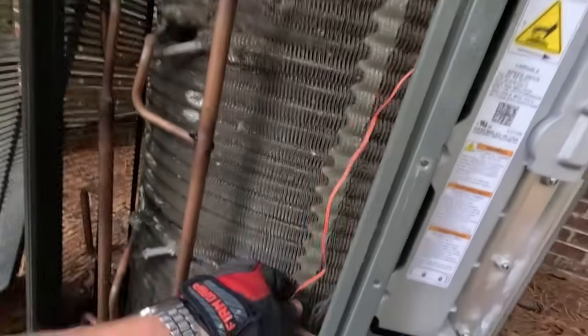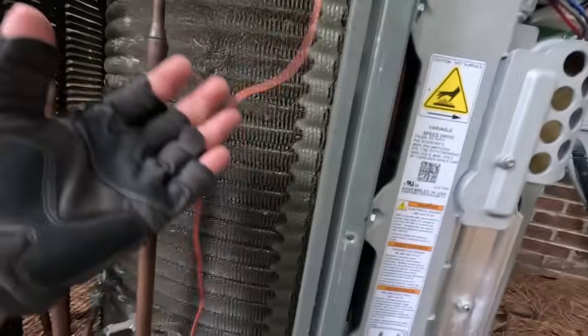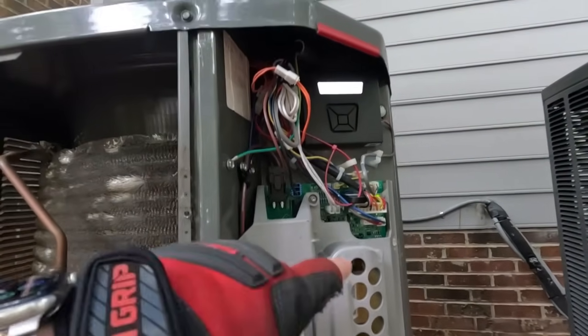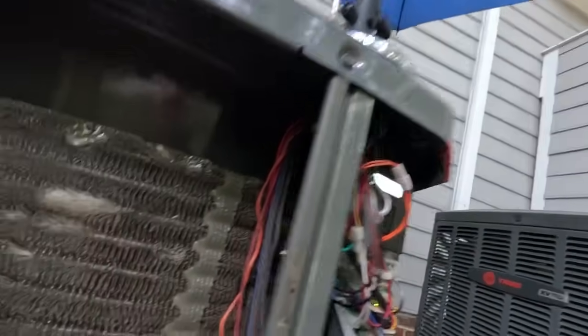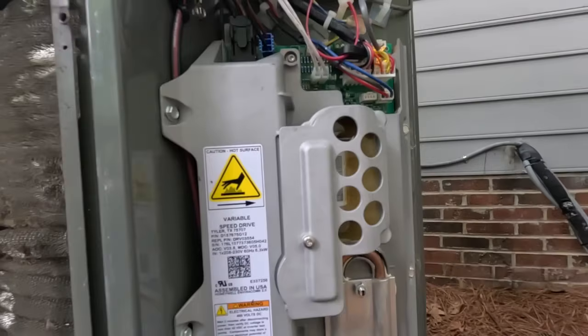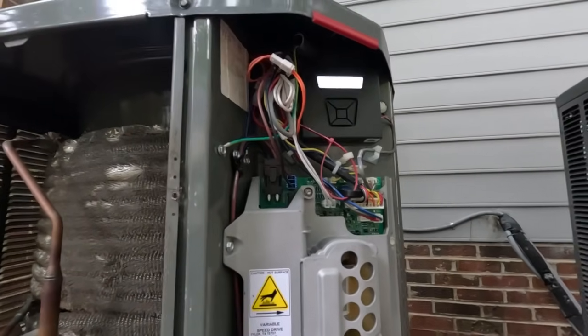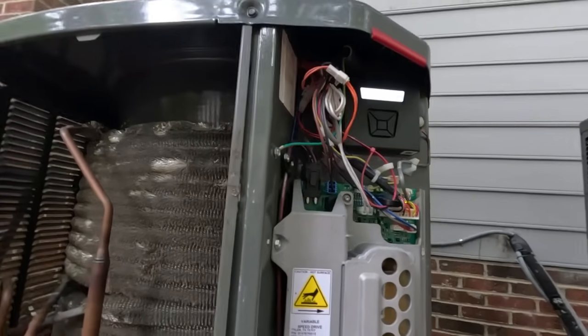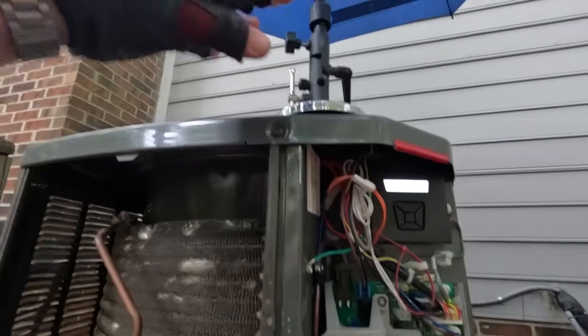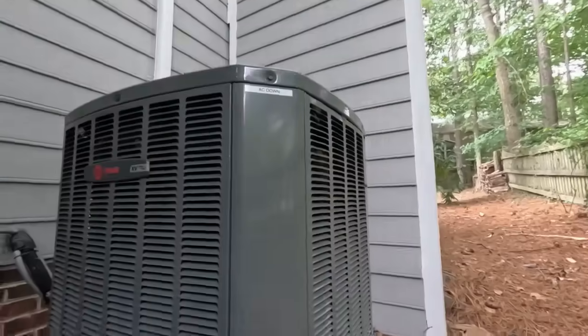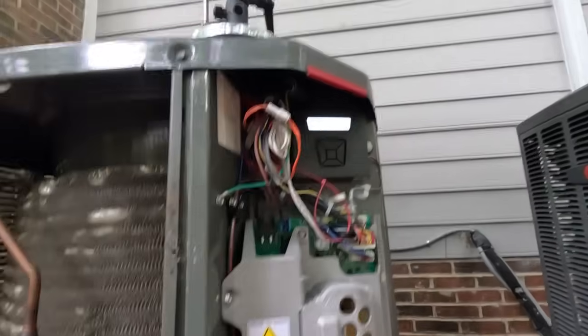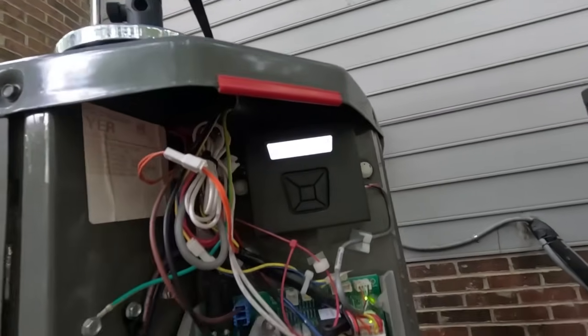So kind of simple, but that's the common problem in these units, not so much the unit itself, it's these sensors in it. So it is what it is. It's better than a compressor going bad or a coil spring a leak. I'm sure that's going to happen in the near future, but I mean, these units, minus the sensor issues, these XV systems, this is the 18 seer, the 20 seer has got the weather guard top on it. He's got two 18 seers out here, one for downstairs, one for upstairs. So it's running real low right now.